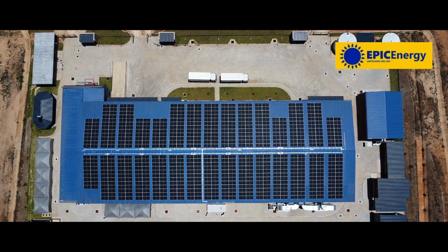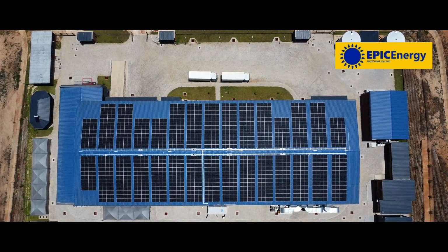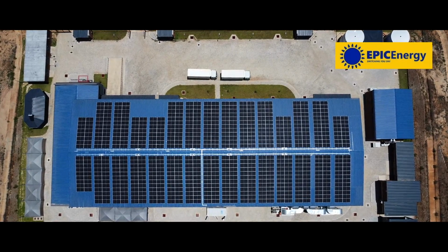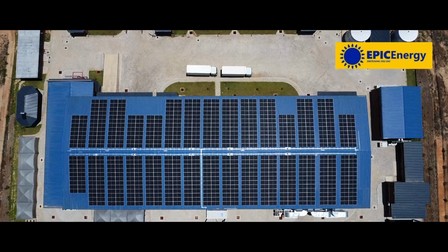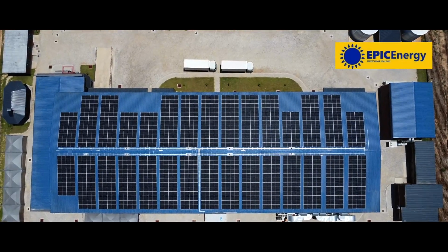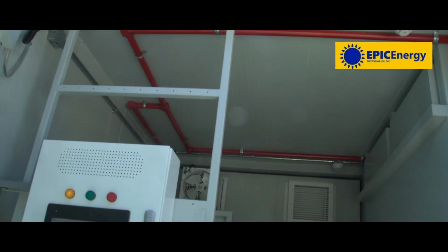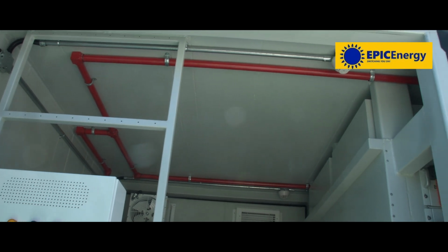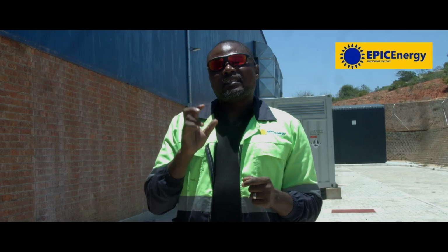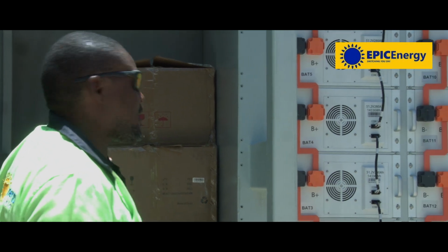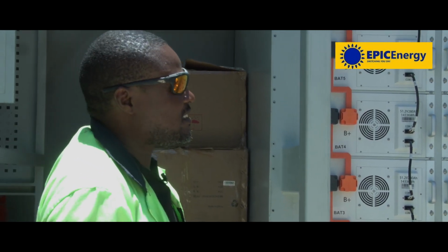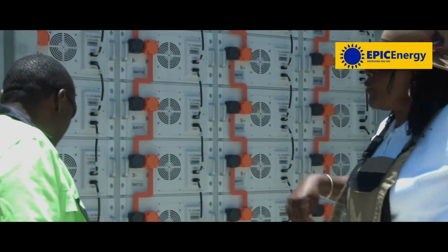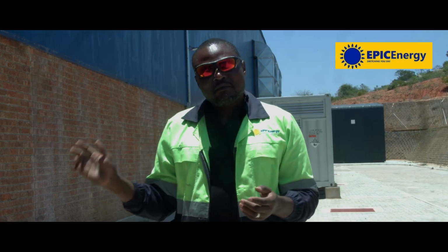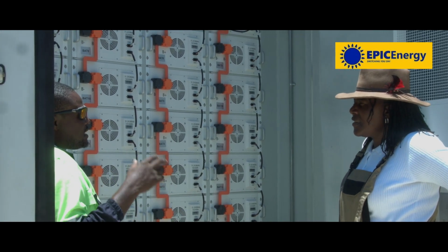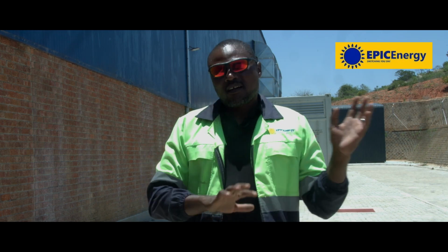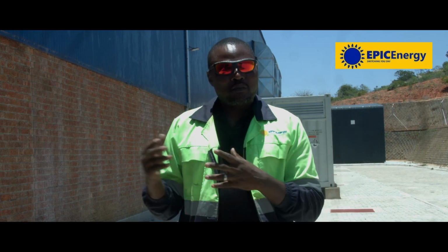Then from there, on the roof, we installed the 370 kilowatt solar array through a firefighter system as well. Basically how this firefighter system works is we plug our solar array into the firefighter system, then from the firefighter system it goes into the combiner box. The reason being, the firefighter systems are controlled by AC input power. So if there is a surge or a fault on the DC side, anyone can quickly punch the emergency button on the wall to make the system shut off production from the solar array whilst we attend to the surge or whatever fault is happening on the system.